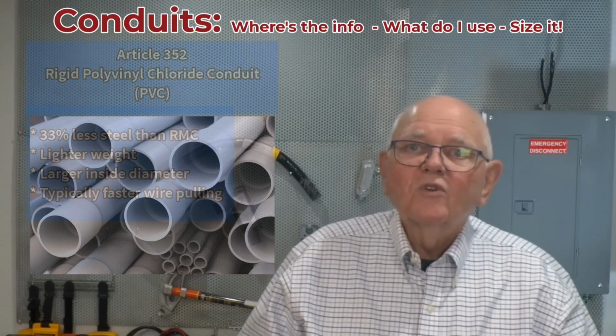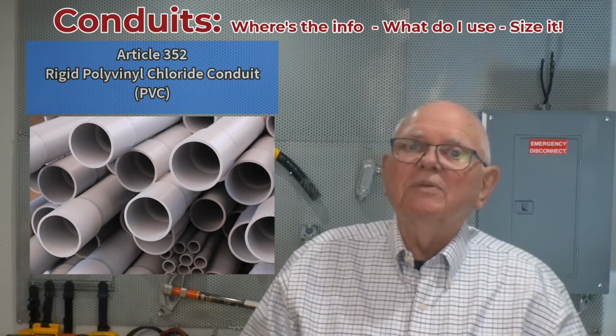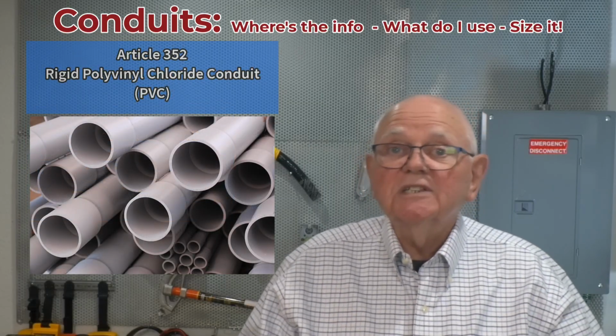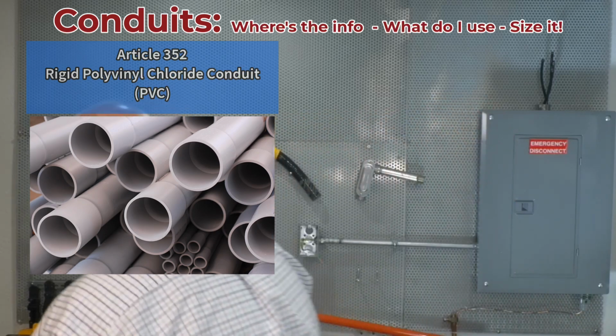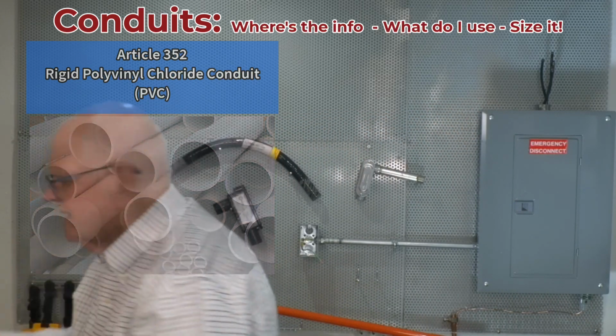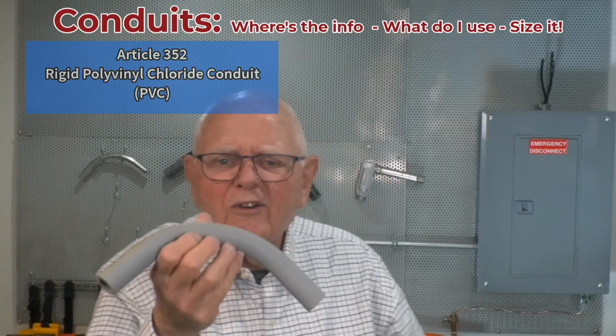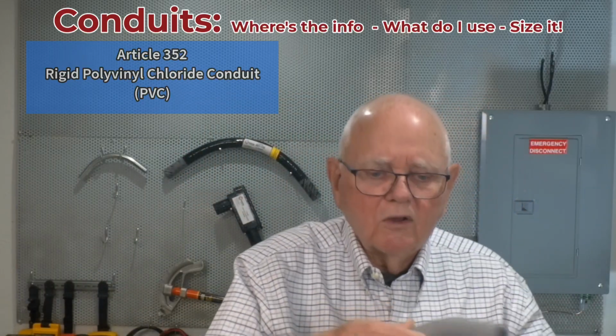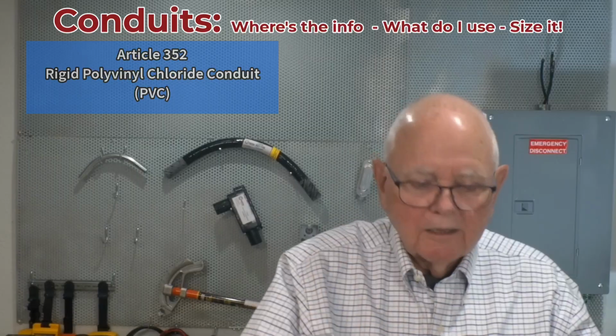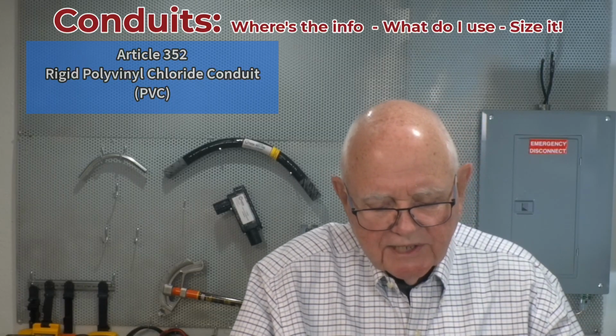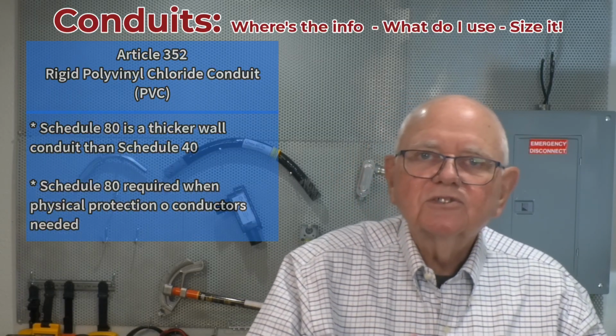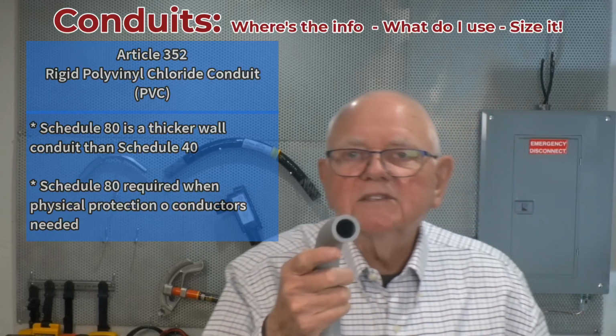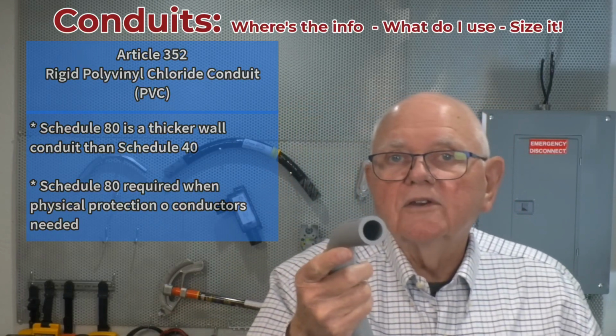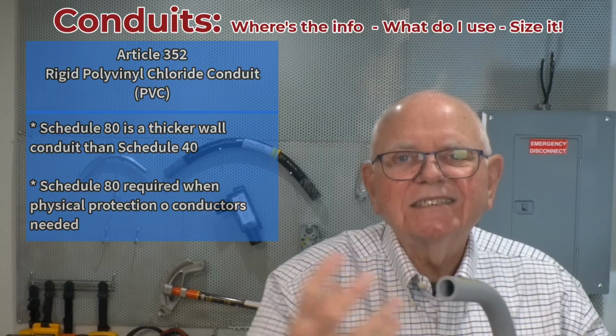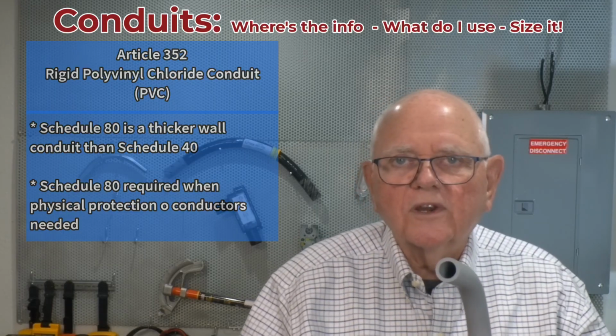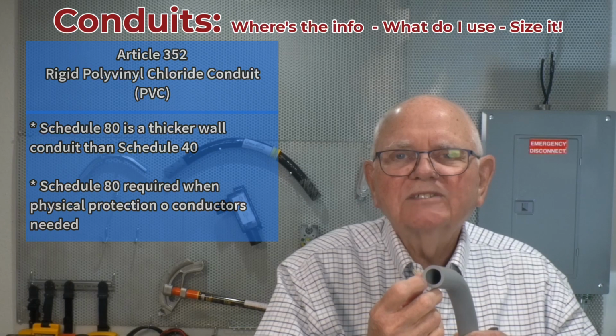Then we have rigid polyvinyl chloride, PVC conduit, right? It's rigid, it's non-metallic, and here's a factory bent elbow. There's lots of information on here, and it tells me Schedule 80. The difference with Schedule 80 is a heavier wall conduit. Same outside dimensions, so my same fittings will fit on the Schedule 40 or the Schedule 80, but the Schedule 80 has a thicker wall.